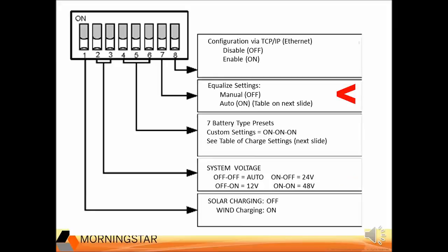Automatic equalize can be disabled with DIP switch 7, but the manual equalize will still operate according to the 4, 5, 6 factory or custom presets. The other custom program settings are enabled with switches 4, 5, and 6 on only.